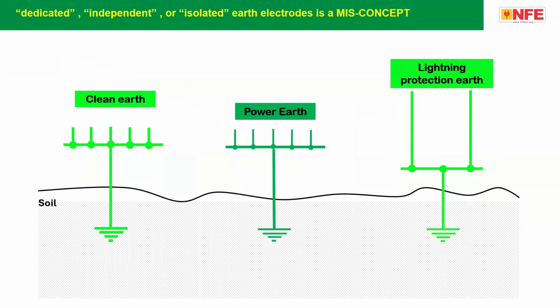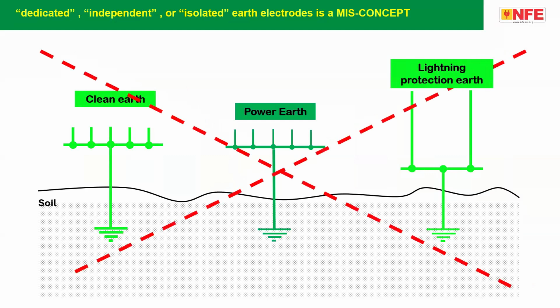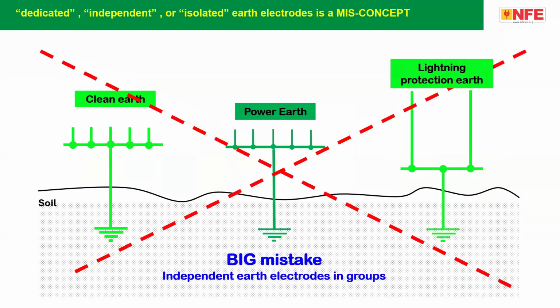Now, the second mistake is the concept of clean earth, power earth, lightning protection earth, separate. This is also a mistake. We have been advocating that. Please note that these mistakes are the main reason for non-operation of protective devices during an earth fault, which is creating failures and fire accidents in the country.